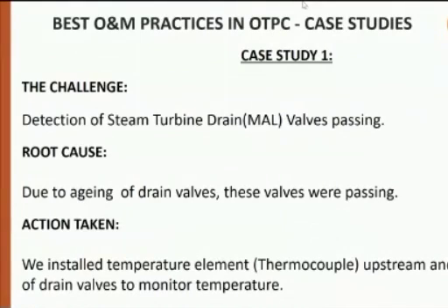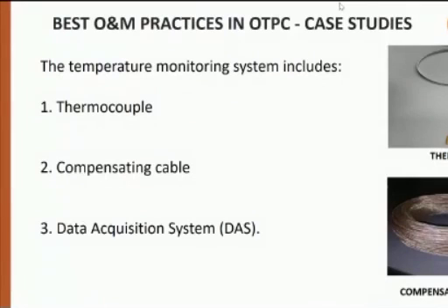What we understood is that there is no monitoring method by which we can find which valves are passing, so that we can plan a maintenance activity for that valve, or close the valve tightly in manual mode. So what we did was install a temperature element, a thermocouple, upstream and downstream of the drain valves to monitor the skin temperature of the upstream and downstream portions of the valves. Whenever we find high temperatures downstream while the valves are closed, we understand that these valves are passing, and we can go to the field and tighten the valve by hand, or plan the replacement of the valve in the next shutdown if the valve does not close properly by hand. The thermocouple, compensating cable, and data acquisition system were installed in the field itself.